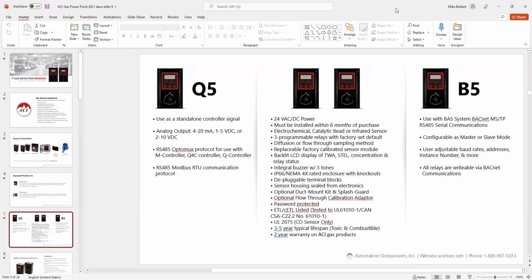The power is 24 volt VAC or DC. I'll let Dave talk a little bit down the road here on AC or DC powering and making sure that everything is square on the power, sharing power transformers and stuff like that. The CO is UL 2075 listed, and typical lifespan on a toxic and combustible, you know, we have to put something down, 3 to 5 years. We've got some of these sensors, CO wise, that have been out for 7, 8 years. It all depends on how stringent the gas is in the area that you're measuring. If it's higher gas consistently, the sensor will wear and the lifespan will come down.